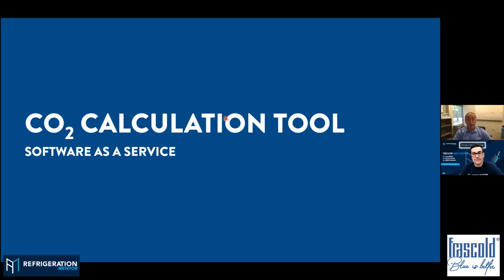But on the other side, we are trying also to go in the direction of some customers that are trying to float the evaporator as much as possible, especially in some applications. So they will never guarantee you the 20K we would like to have. So it's always a compromise. And on the other side, we don't even want very high superheat, because in our application it can result in a higher discharge temperature, especially when the suction of the second stage compressor is the discharge of the first. So we want to stay somewhere in between.